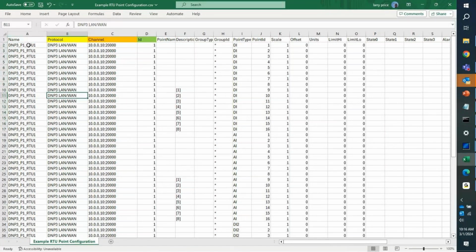You can use some default information, but what is critical is your protocol, your channel. A channel is a new parameter that you'll see in the test set, both in task mode and exchange mode. In that field, you can specify the IP and port associated with that RTU.